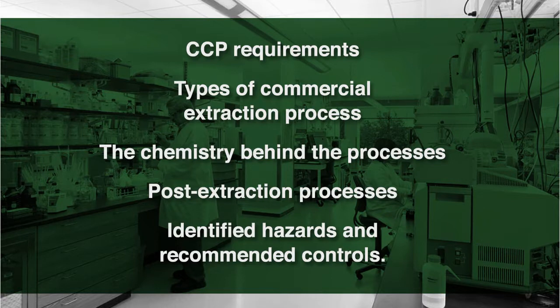We have to make sure that the gas detection equipment has been installed properly and has been calibrated. The same thing with the ventilation equipment. So if they have, for instance, a fume hood, we'll test the face velocity of the fume hood and look at what's called the test and balance, the TAB sheets, to make sure that the HVAC contractor did what they're supposed to do.